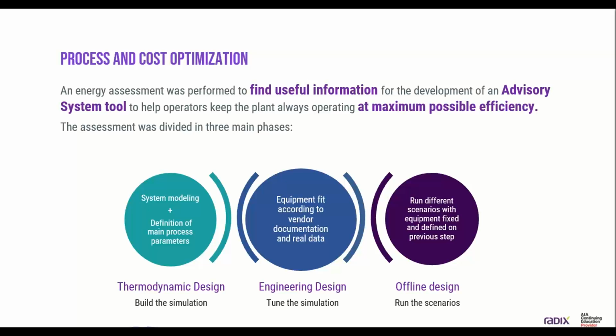Next we did the engineering design, where we tuned the simulation by converging the equipment fit according to vendor documentation and comparing with real-time data. Last but not least, we did the offline design. So after modeling and comparing with past data, we ran different scenarios with the equipment to define when it's best to run each piece of equipment, and when it's best to run at full capacity or at less capacity.